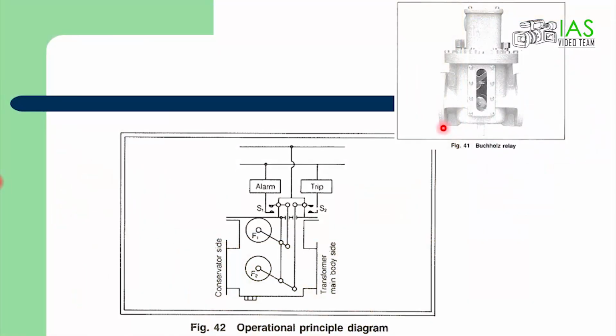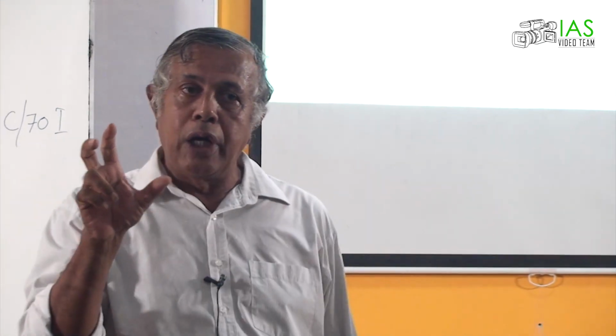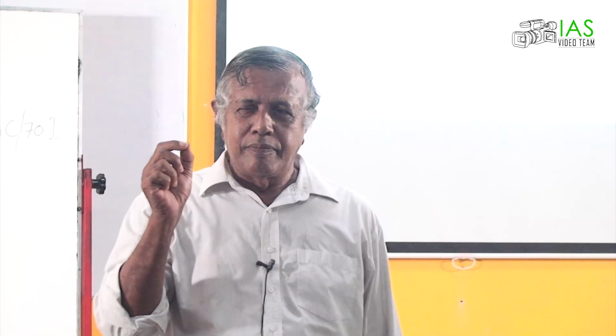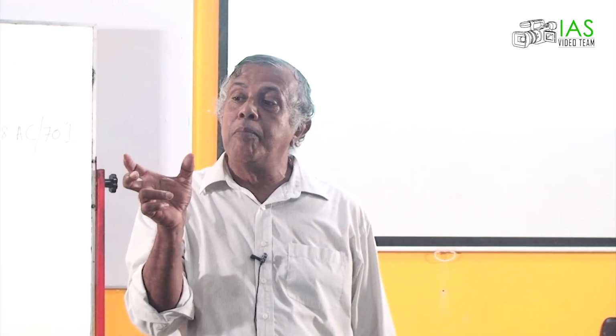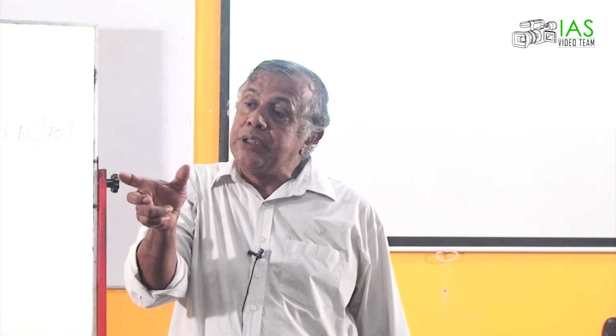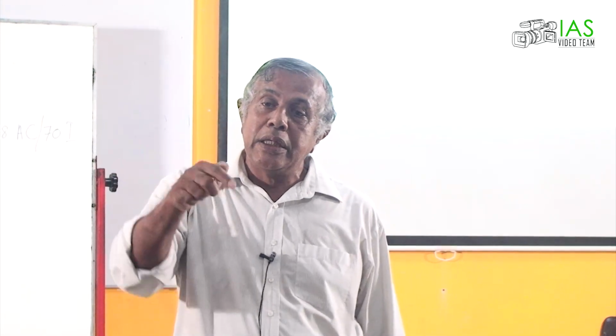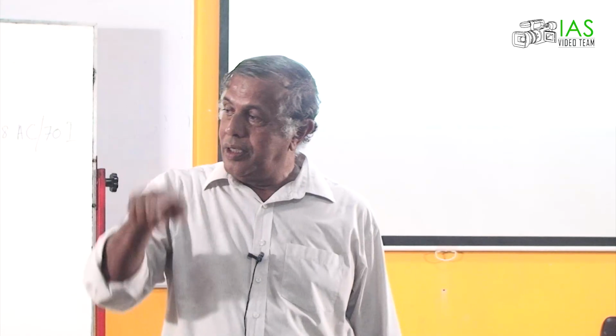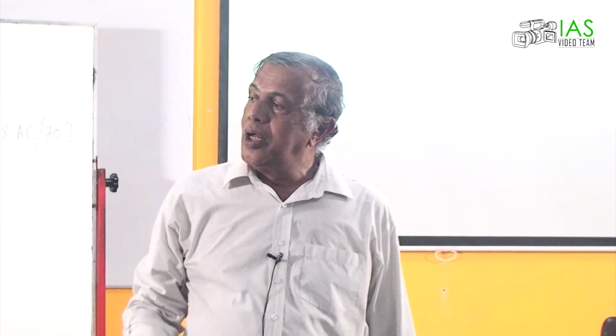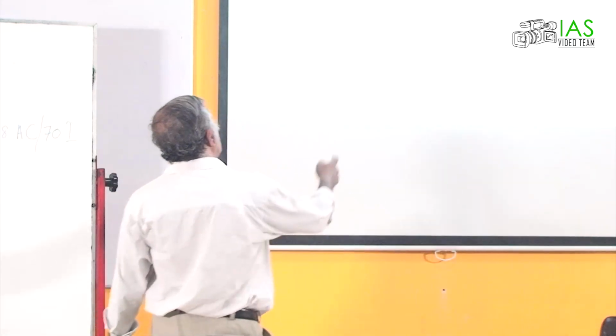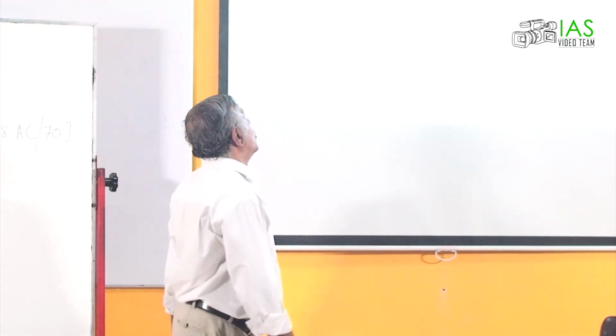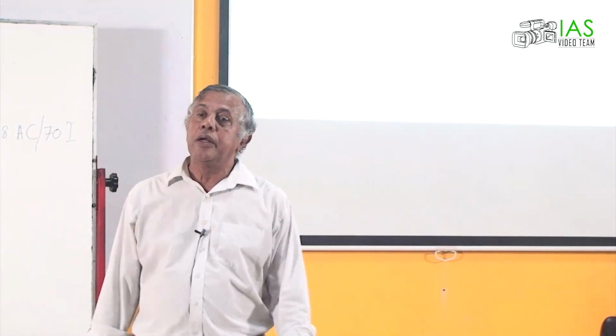So this is a Buchholz relay. This has two actuators. These two actuators are generally mercury bulbs. When the mercury bulb turns to the other side, it completes a circuit. That's how these two operate. Now, one is for alarm and one is for tripping.